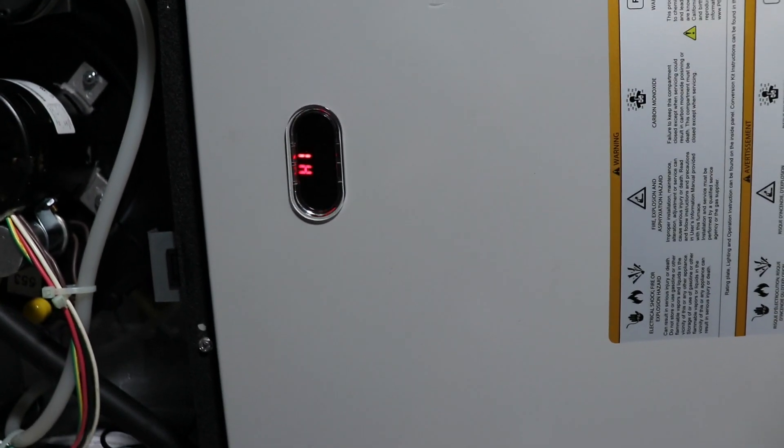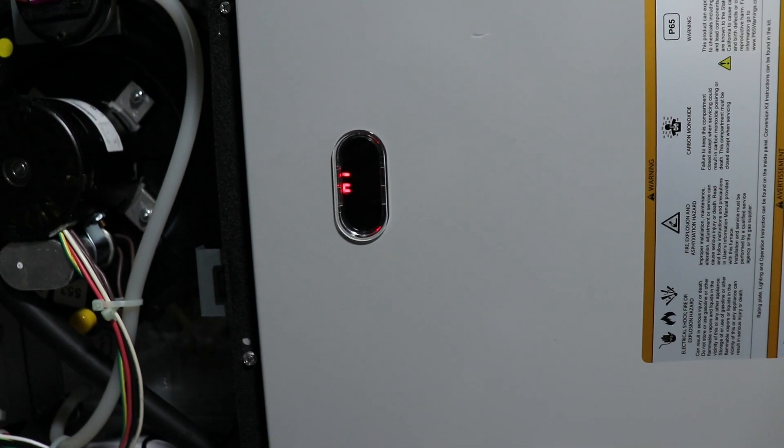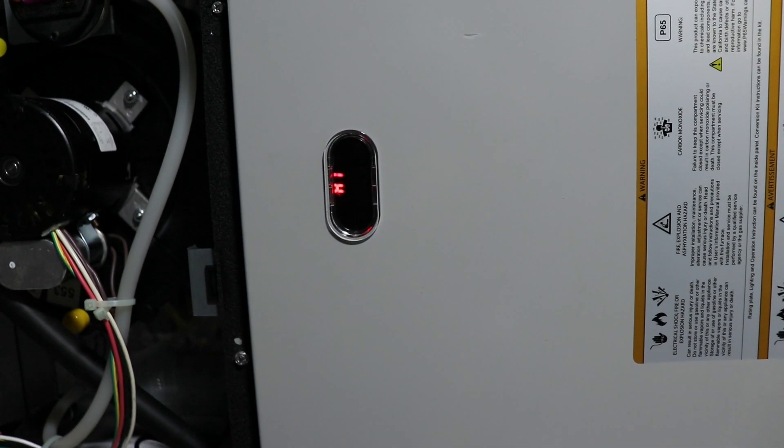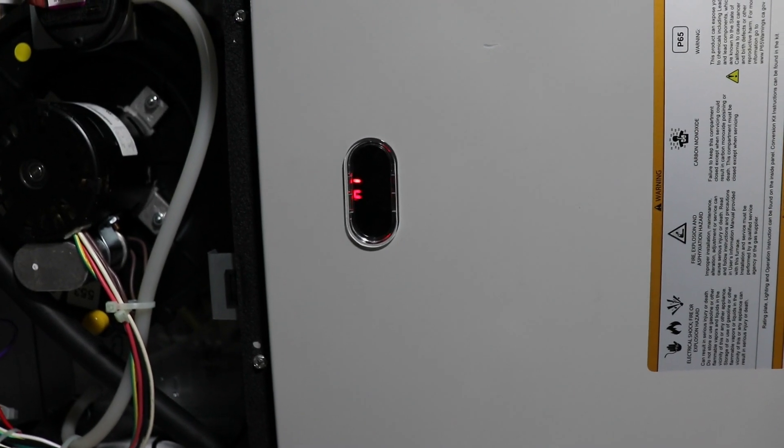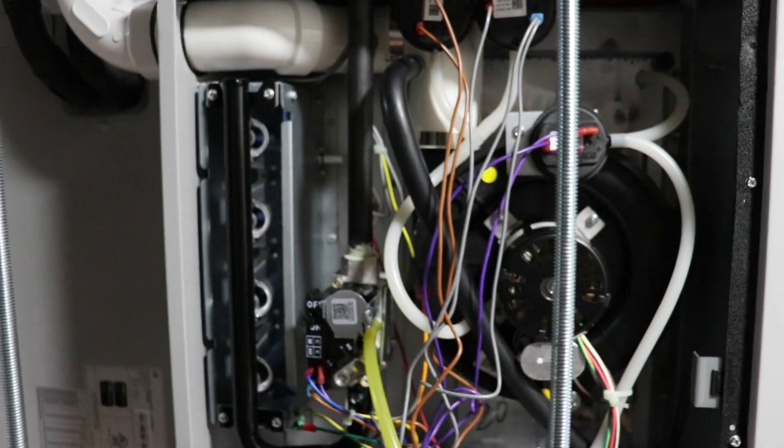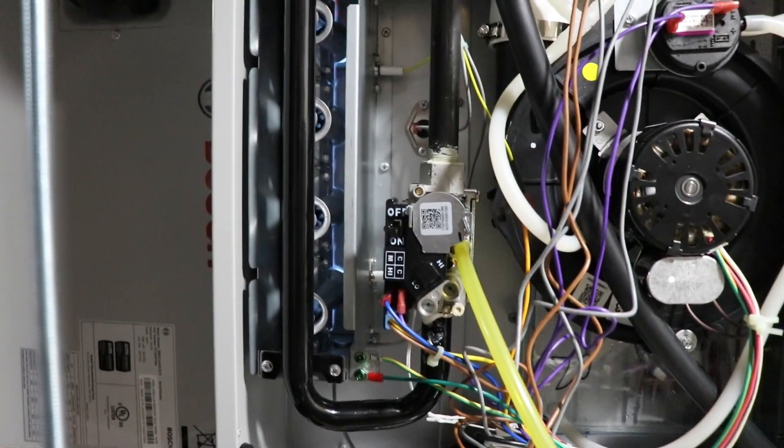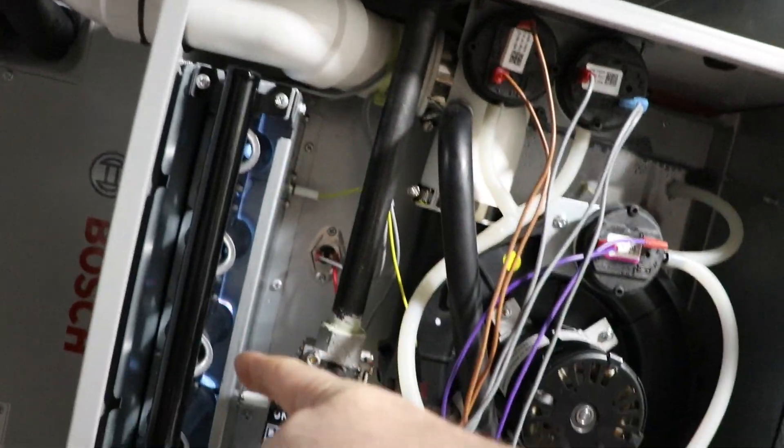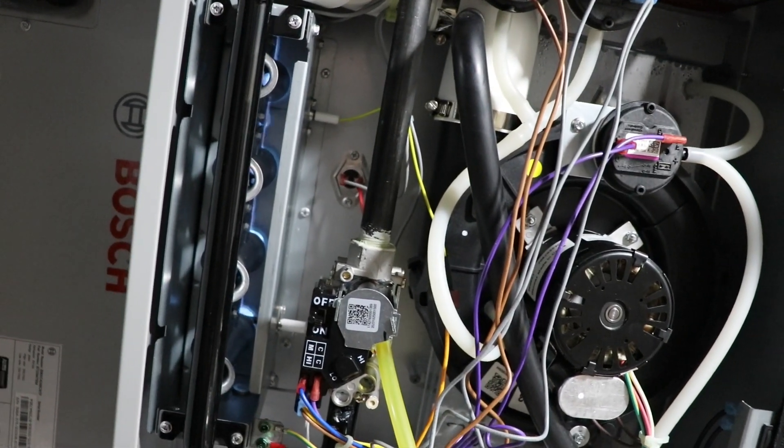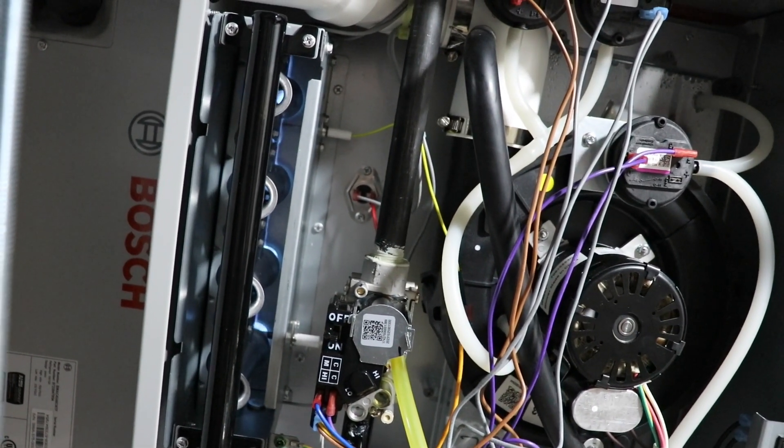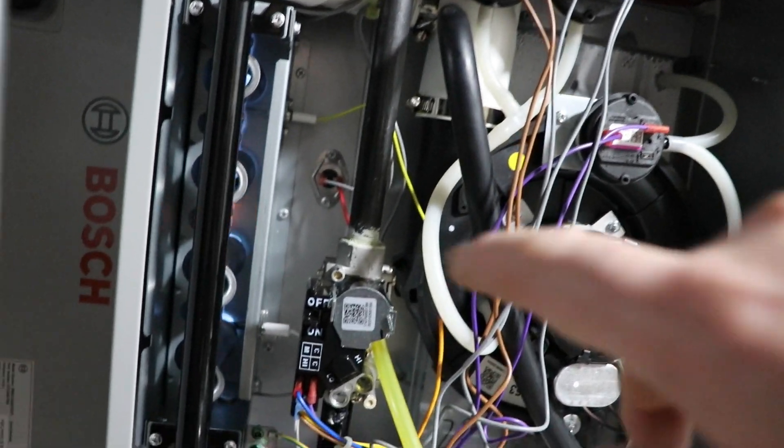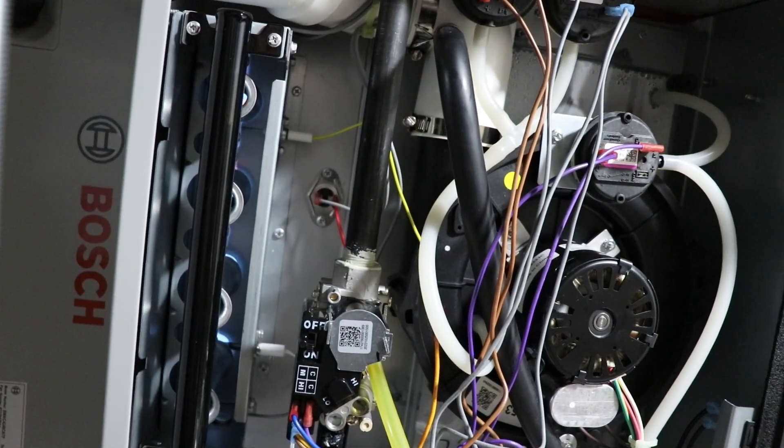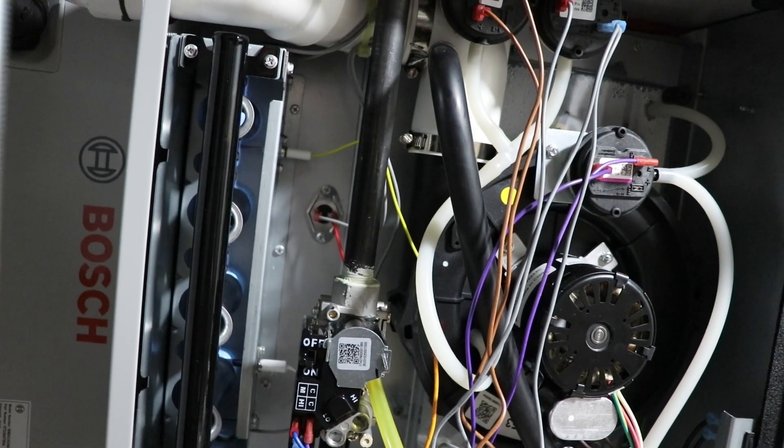I was reading the troubleshooting guide for it, and it's a lot better because it doesn't lump all of the sensors together. There's like two rollouts here to tell if the flame is coming out of the burner. There's another one here for saying if the heat exchanger is overheating. I believe that's the one that's opening.